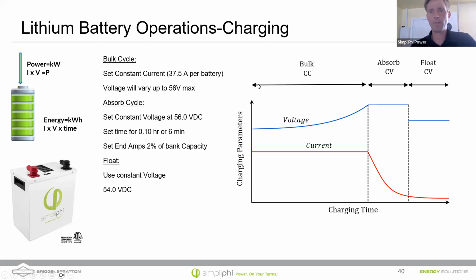Those are more common batteries. So the bulk portion occurs. Notice that the current is just flatlined at a constant value here. That's the bulk cycle. Now, if you had 2 batteries, you would double that 37.5 for 75. If you have 10 batteries in parallel, it would be times 10. So you could charge 10 of these batteries at 375 amps. But that's done in a constant current.